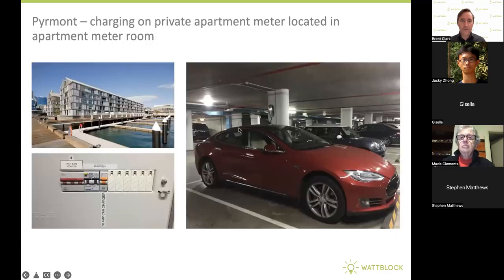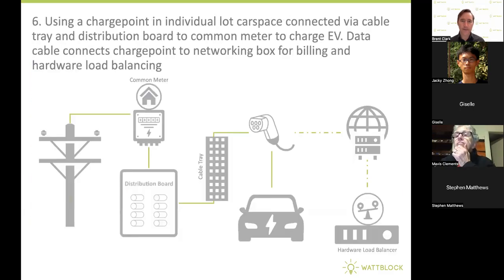Here's an example in Pyrmont where the meters were in meter rooms adjacent to the car park, on the same level as the parked cars. The charge point is on the wall, with conduit along the roof going to the meter room, and a breaker for the individual apartment meter there to allow charging. That comes off the individual apartment meter, so there's no need for cost recovery.